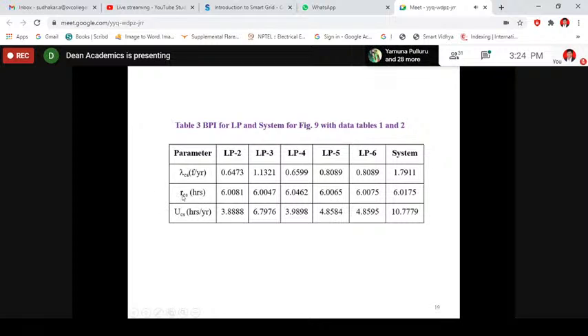RCS is the average outage time for load points 2, 3, 4, 5, 6 and the system. UCS, most people refer to it from the consumer perspective, meaning load points only. But for at least one of the consumers, you have to consider the system also, the power system point as well. So UCS is average annual outage time, and that is why the units are hours multiplied by failures per year, giving hours per year. So lambda CS into RCS gives UCS.